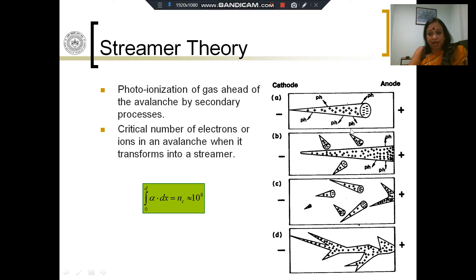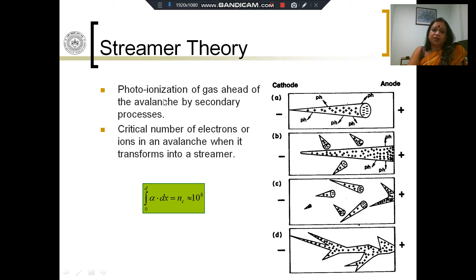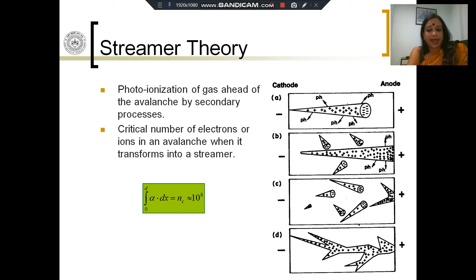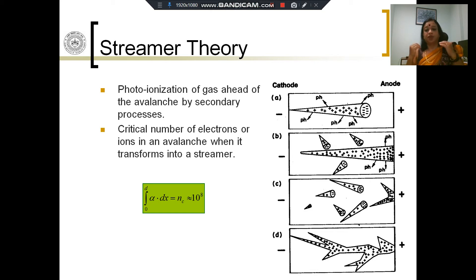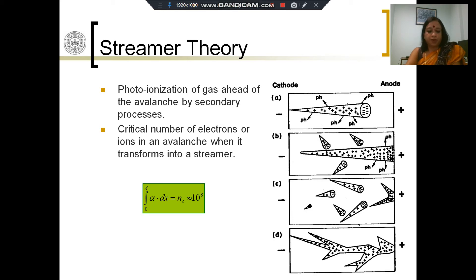These discharges that are created due to the photoionization are called Streamers. The critical number of electrons is given by this relationship: the integral of alpha dot dx, from zero to d — zero to d being the gap distance — must be equal to a critical number which is 10 to the power 8. We need at least 10^8 electrons at the head of the avalanche so that we have enough space charge modification, enough space charge accumulation, such that the local electric field will be enhanced, and the local field enhancement will cause photoionization. The Townsend mechanism will now give over to the Streamer mechanism.